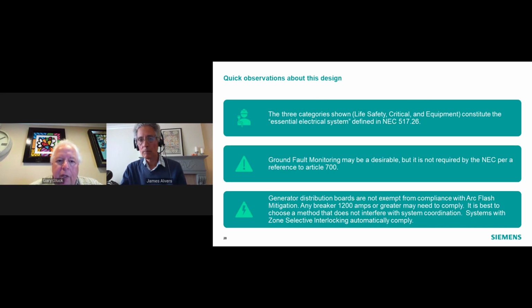All right, just a quick observation about this design. The three categories shown, life safety, critical, and equipment, constitute, like I said, the essential electrical system defined in 517.26. Ground fault monitoring may be desirable, but it is not required by the NEC per reference to Article 700. And generator distribution boards are not exempt from compliance with arc flash mitigation. Any breaker that's 1200 amps or larger may need to comply. And it's best to choose a method that does not interfere with the system coordination. So zone selective interlocking is actually a really good choice for compliance, as it does not interfere with the normal coordination in the system.